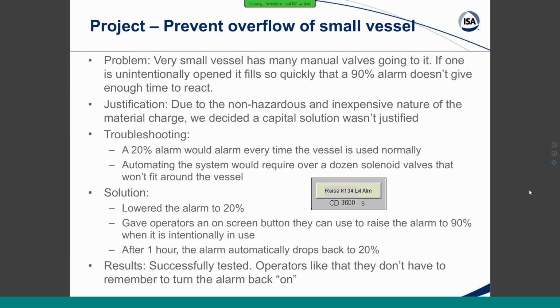So the alarm has been lowered to that 20%, and when the operators need to go out and use it as a charge vessel, they can put a 1-hour snooze on that alarm. It raises it up to 90%, counts down, with the little countdown seconds there, and when that hits 0, the alarm will drop back down to the 20% level. This has been working well, and the operators really like that they don't have to remember to turn it back on again after they get done with the charge operation. They can just let it time out, and it will go back to where it needs to on its own.